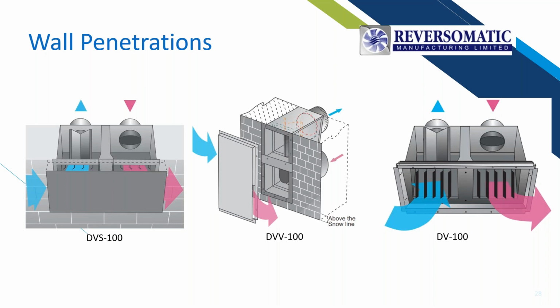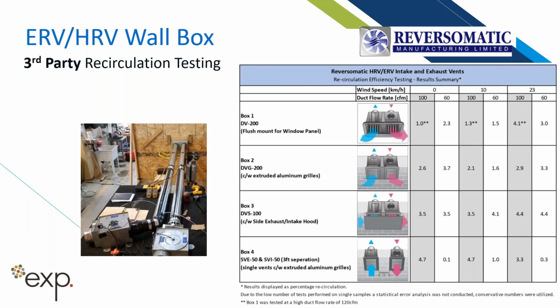We have a few different options, and all of them are third-party recirculation tested. They use a gas tracing technology. You can see the setup there on the left. And by the way, we have a wind speed across this of up to about 15 miles per hour, which is 23 kph, where the unit is tested at different flow rates between 100 and 60 CFM, which is pretty common, and none of them even meet half of that 10% requirement.